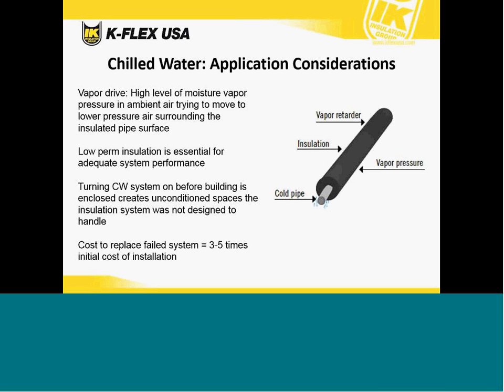Some watch-outs here are also to turn on a chilled water system before a building is enclosed. This may create an unconditioned space that the insulation system was not designed for. The system is designed for indoor applications and the building is not fully enclosed. The temperature and humidity values may be at a point where condensation will occur even if the insulation is already installed. With a fibrous or any type of open cell insulation system in this case, you start getting moisture penetrating into the insulation system from day one, which could cause performance issues later on in life. And just a quick takeaway here as well, to replace a failed system is generally 3 to 5 times the initial cost of installation.